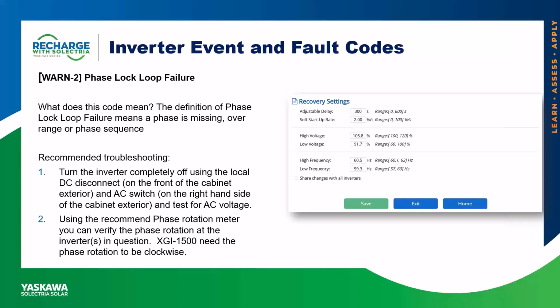Now, especially in the event you are able to measure voltage at the customer connections inside of the inverter cabinet, the issue at that point is possibly phase rotation, at which point we recommend to see if this code is isolated to just one inverter or the entire pad, as the simple solution is to rotate any two phase conductors, for example, phase 1 and phase 2, L1, L2, phase A or phase B. Where that takes place can either be at the distribution panel or the inverter cabinet. It just depends on the extent where you're seeing the codes.